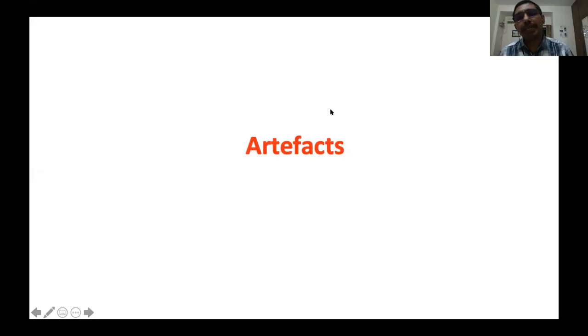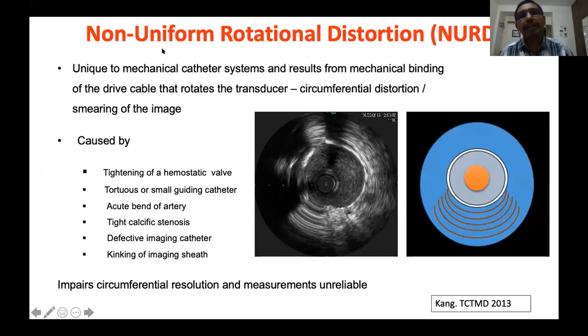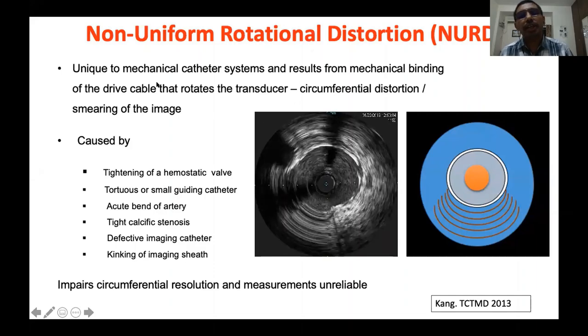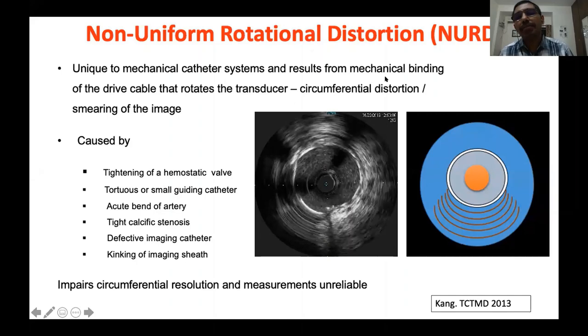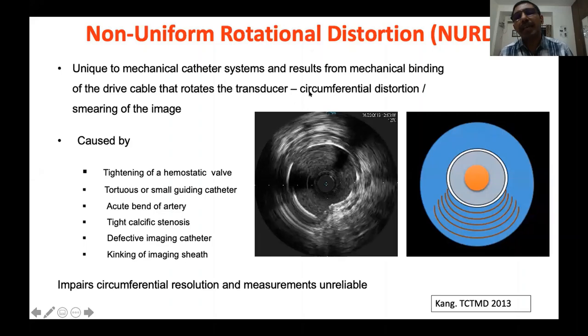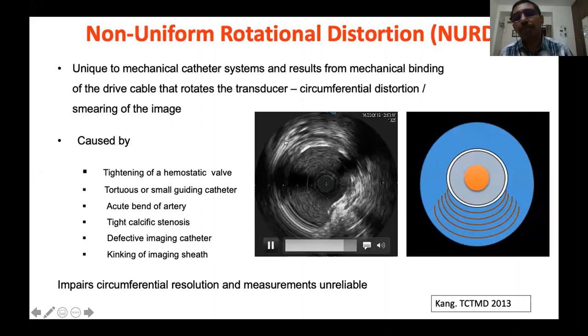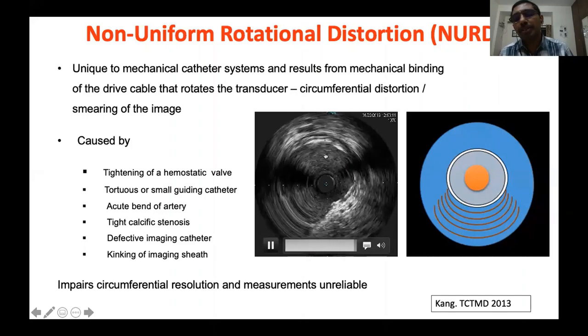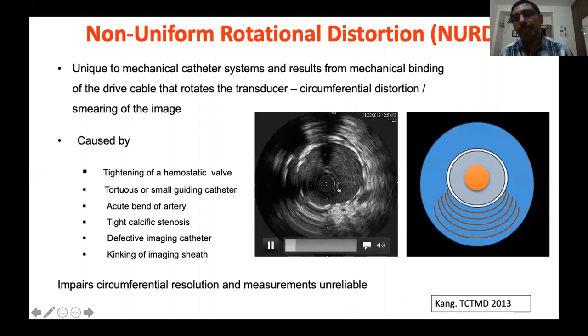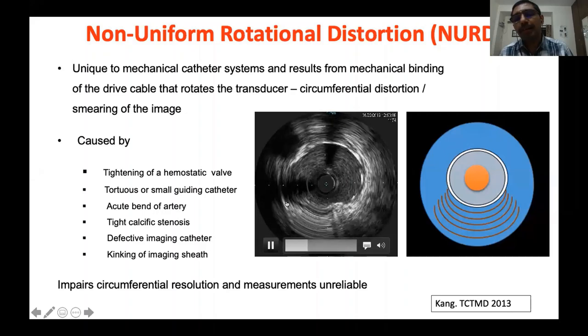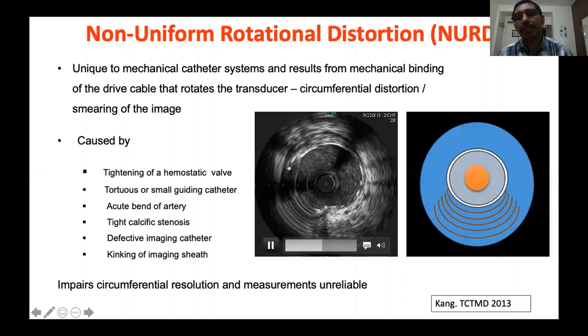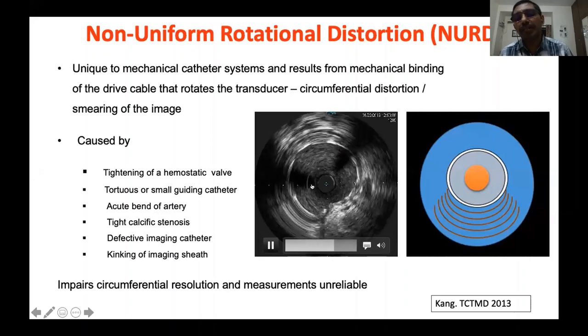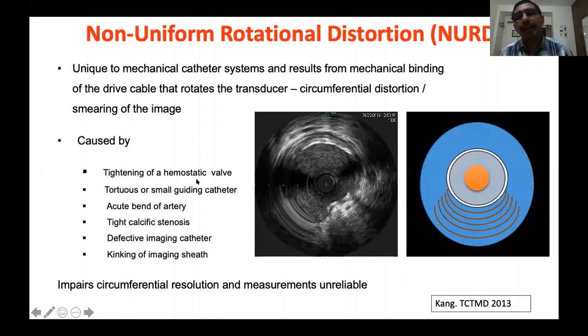This completes image interpretation. Now the last part — image artifacts. It is very important to understand image artifacts to avoid mistaking them for normal anatomical or pathological structures. The first artifact is Non-Uniform Rotational Distortion (NURD) — unique to mechanical systems. It results from mechanical binding of the drive cable that rotates the transducer, causing circumferential distortion or smearing of the image. If part of the rotation is constrained, it produces an onion peel-like appearance — that is non-uniform rotational distortion.